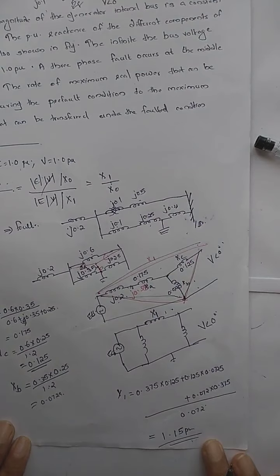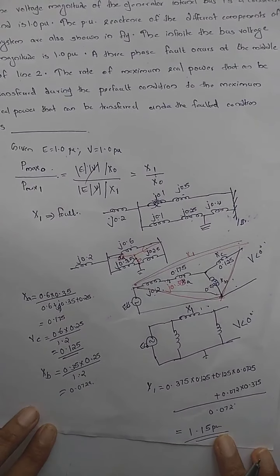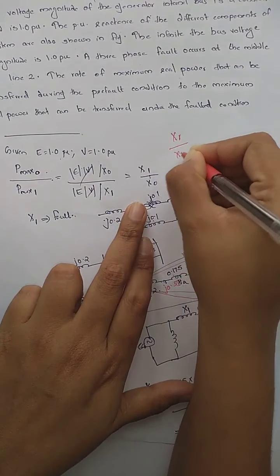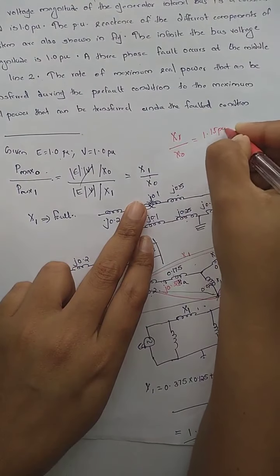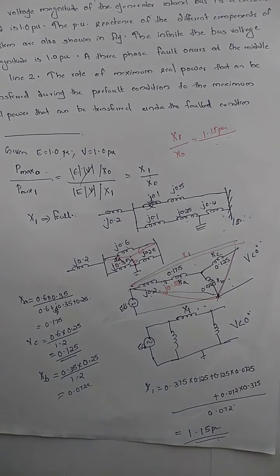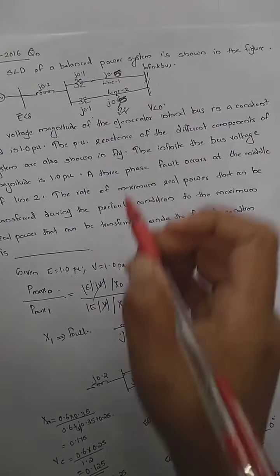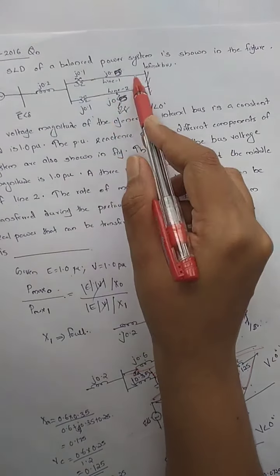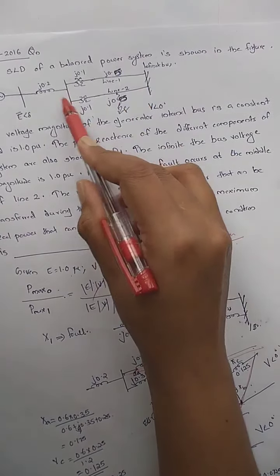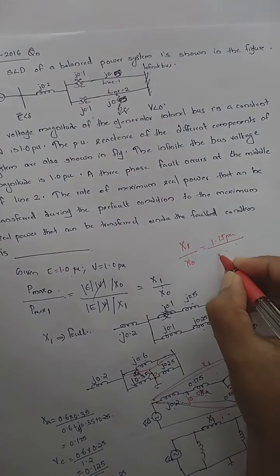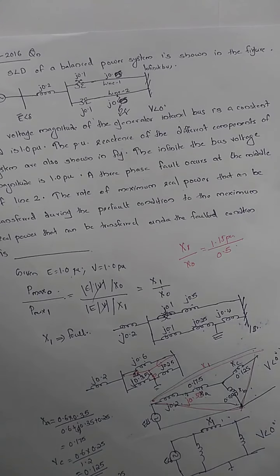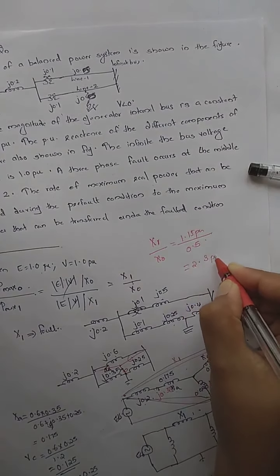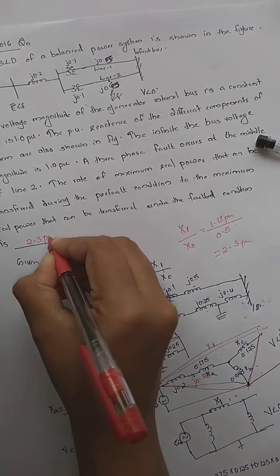The X1 value is 1.15 per unit. Now finding X0 under the steady state pre-fault condition: 0.5 plus 0.1 equals 0.6 for each line path, and 0.6 in parallel with 0.6 gives 0.3. Adding 0.2 gives X0 = 0.5 per unit. Therefore, the ratio X1/X0 = 1.15 / 0.5 = 2.3 per unit.